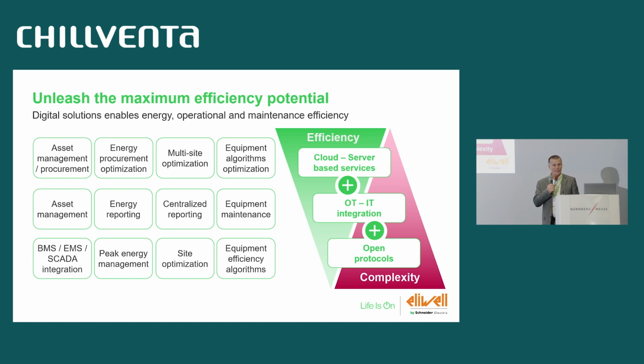But there's another topic that I think is important to consider, which is maintenance. The higher we go in integration, the more we're capable of doing better maintenance, or optimizing maintenance. Maintenance means we manage the wearing of the system. We have a reduction typically in performance for mechanical reasons - dust on the condenser, just to be simple - but we may also have loss of performance, for example because we don't adapt to climate variation.